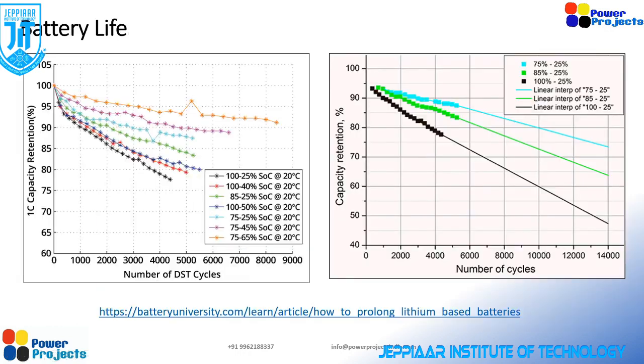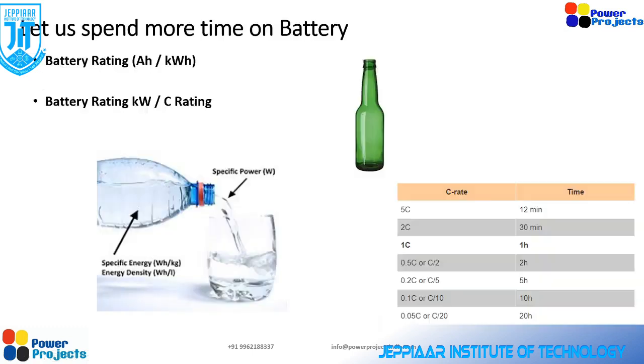If you compare, with 75% to 25%, meaning running at 50% depth of discharge, the blue line shows that even after 10,000 cycles, the battery is able to retain about 80% of the capacity. But you need to note that this is at an ambient temperature of 20 degrees Celsius.